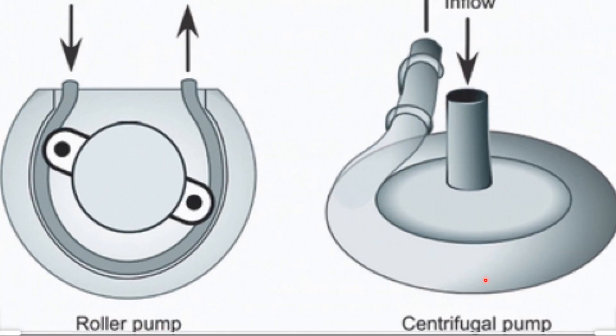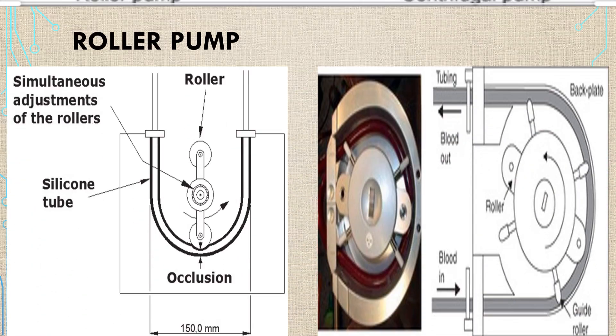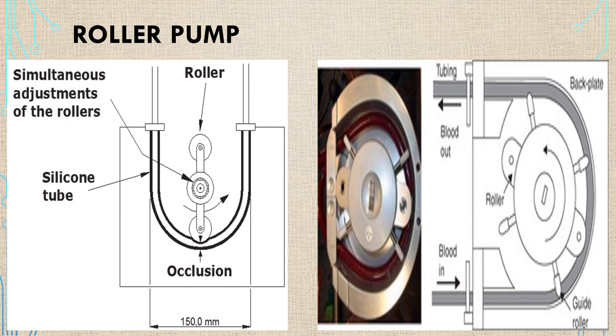There are two types of pumps: centrifuge pump and roller pump. This diagram explains the roller pump. It has silicone tubes where blood flows in and out, and there is an occlusion mechanism within the pump.